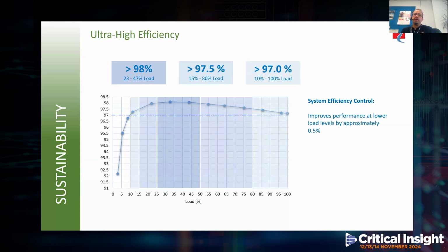Now, a very important point in relation to the efficiency curve that you see here is that all of the figures shown are with the UPS operating in true online mode. These are not average figures as used by some manufacturers. When we say the average figure, typically what some manufacturers will do is use the average efficiency, which is effectively a mix of both online and eco modes over a fixed period of time. So it's not really a true representation of most real world conditions. I mean, let's be honest, most operators are going to be running their online dual conversion UPS systems in online mode for maximum protection.